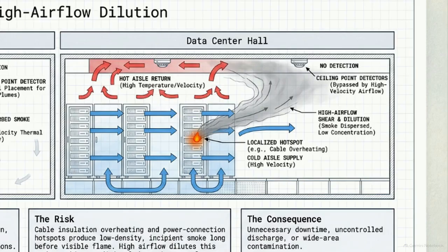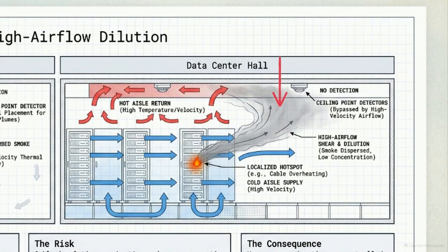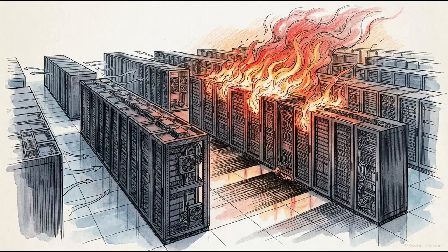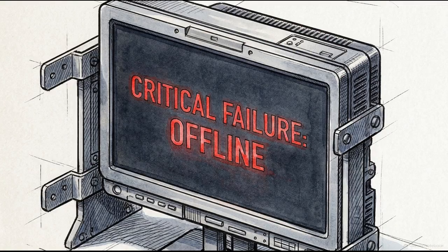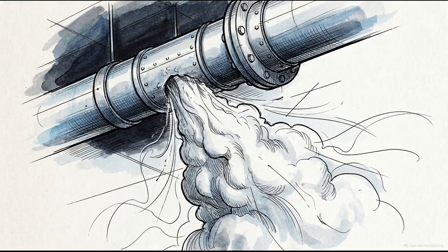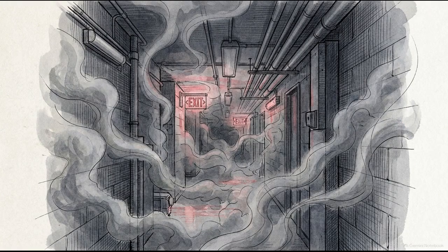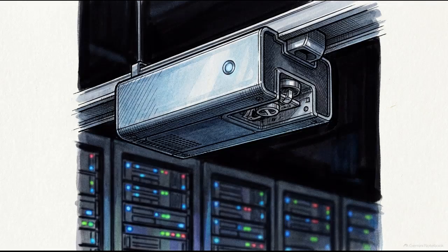Data halls operate under different physics. High-velocity cooling air, specifically cold aisle supply and hot aisle return, creates high airflow shear and dilution. This disperses the incipient smoke so effectively that it bypasses traditional ceiling detectors entirely. This detection failure leads to unmanaged fire growth, resulting in facility downtime, uncontrolled suppression discharge, or wide-area smoke contamination. Passive point detection breaks a facility's business continuity and life safety strategy in high airflow environments.